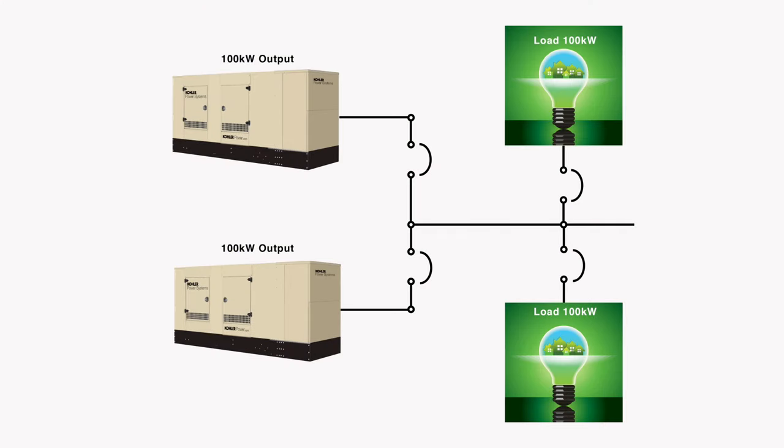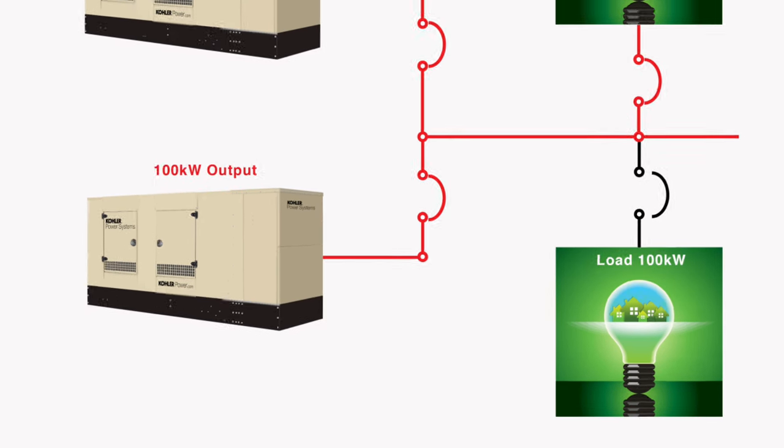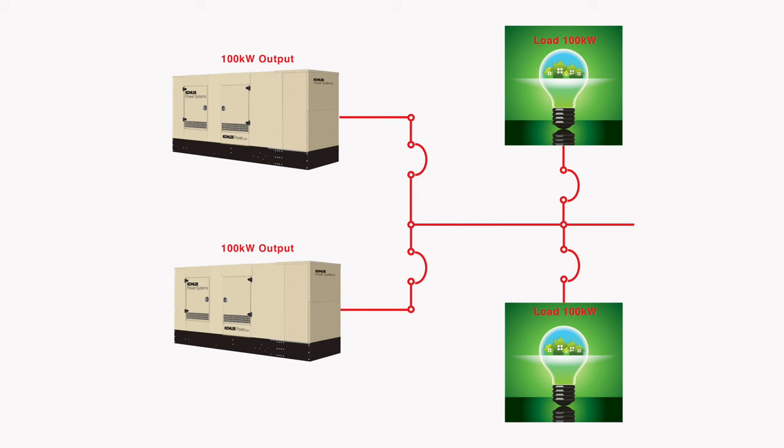For one, when two smaller sets are used instead of one large set to manage a large intermittent load, one set is run in parallel as load varies. Lightly loaded engines are susceptible to wet stacking.